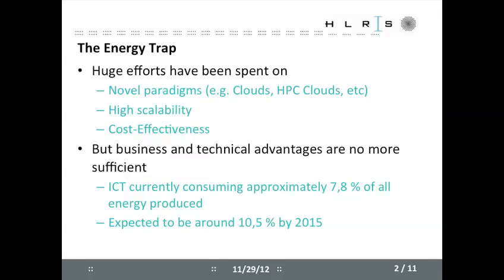What we are currently seeing in HPC systems, cloud systems, and storage is that we try to make data centers more efficient. For example, we try to get better cooling to reduce costs. In our HPC facility, we have nearly 50% cooling costs compared to the compute power we have. We can also reuse the heat from HPC systems for heating our buildings in winter, which is very efficient. For example, in Munich they just installed a new petaflop system where they reuse the heat from the computer for their buildings. But this has one problem — it's just for one data center, it's local, and we could do much better if we did this on a global scale.